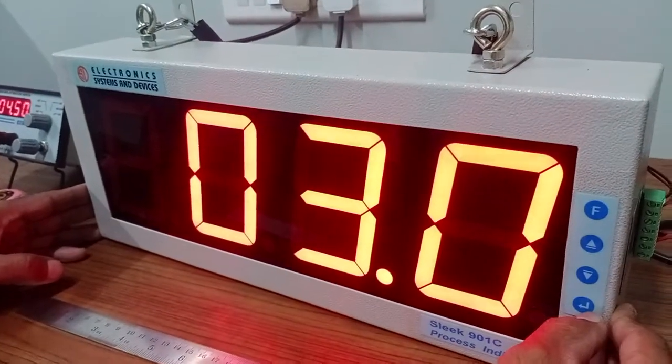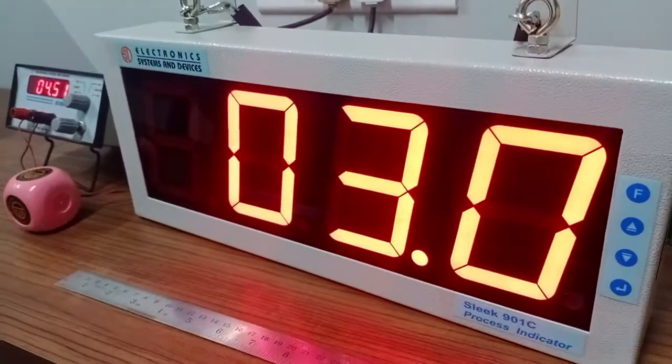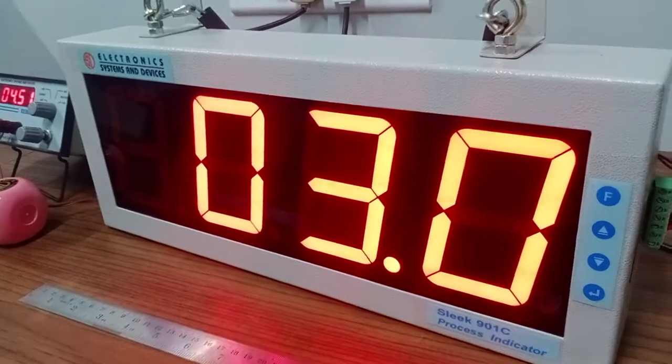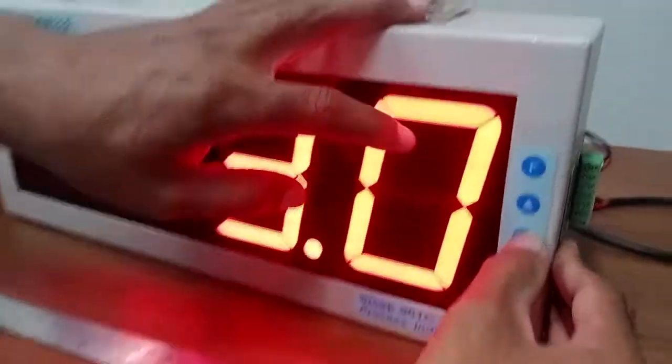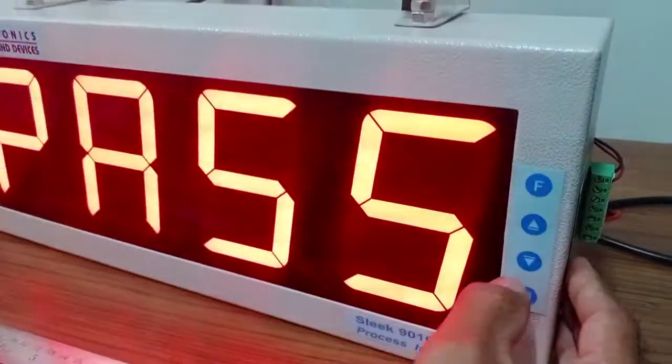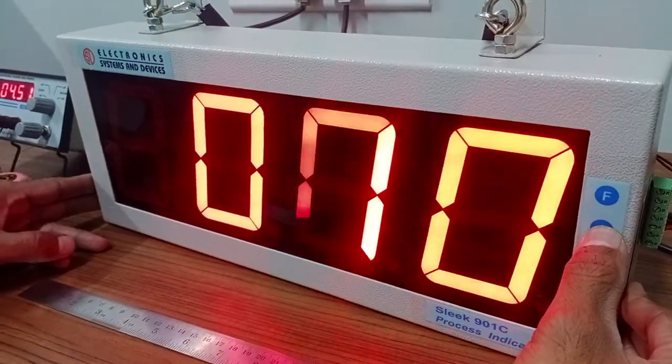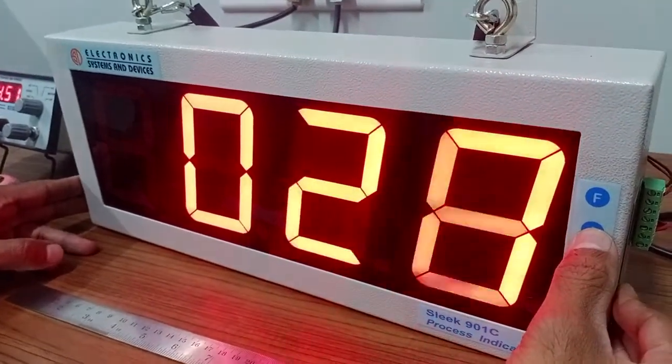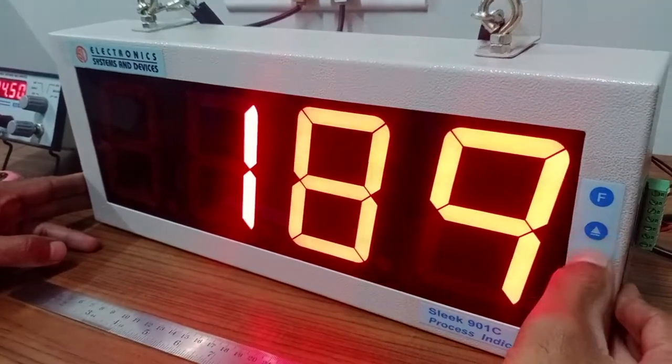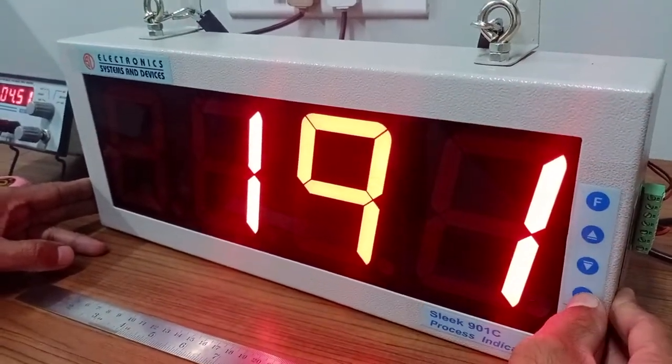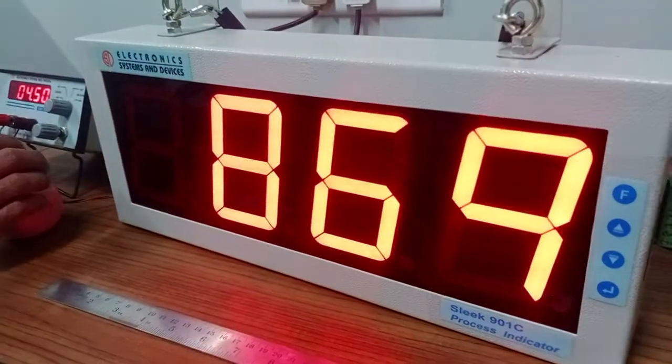Okay, we'll see the calibration mode for this. For calibration, you have to press the decrement key and then press the function key. It will ask for the password. The default password is 191 for calibration. You press enter, it will give a write message.